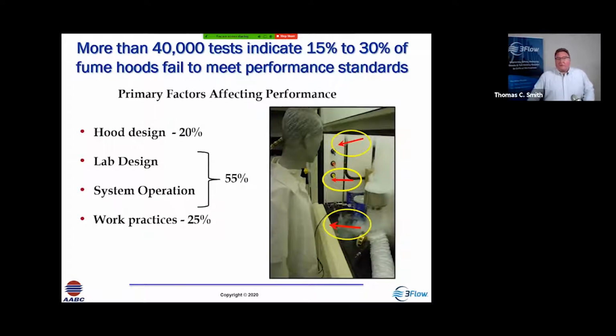So at 3Flow, we've conducted over 40,000 tests on hoods throughout North America. And when we look at the data retrospectively, we see about 15 to 30% of hoods fail to provide adequate containment in accordance with the ANSI Z9.5 standard. And those factors that influence the ability to contain are associated with the design of the hood. Does it have the appropriate aerodynamic qualities? We look at the lab design and operation of the system to make sure that they're proper and appropriate for containment. And then finally, work practices. So lab design and system operation by far indicate the greatest potential for problems. And so we really have to focus on how we ensure that the systems are operating properly and are conducive to proper hood containment.